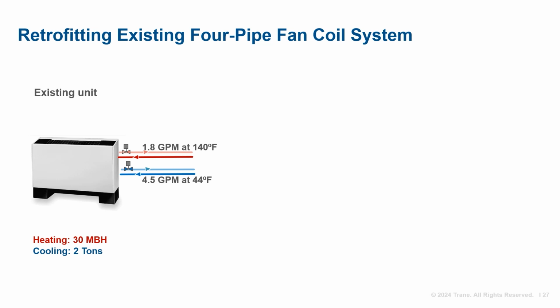Let's look at an example replacement scenario for this type of fan coil. The existing equipment has a 2-row preheat coil using 140-degree hot water and a 2-row cooling coil using 44-degree chilled water. The delta T for heating is 33 degrees and for cooling it is 10 degrees.